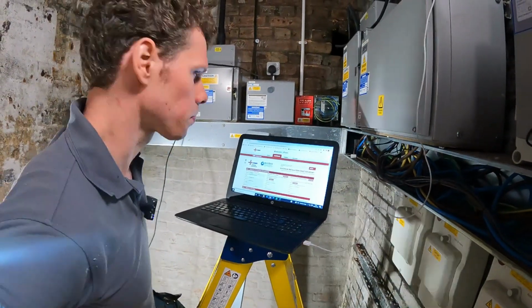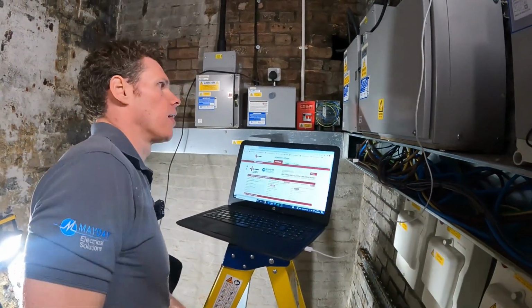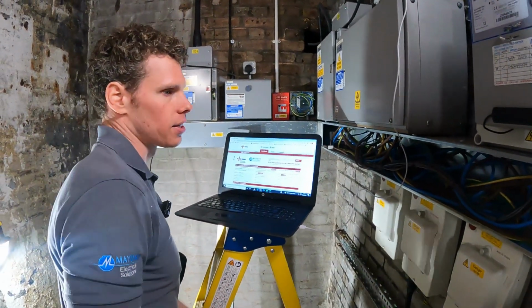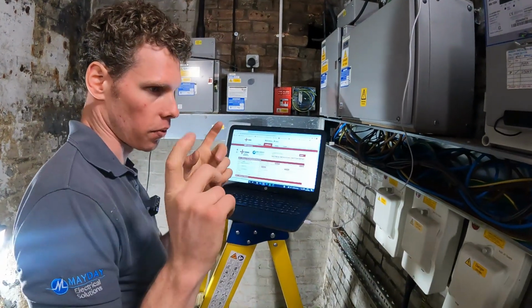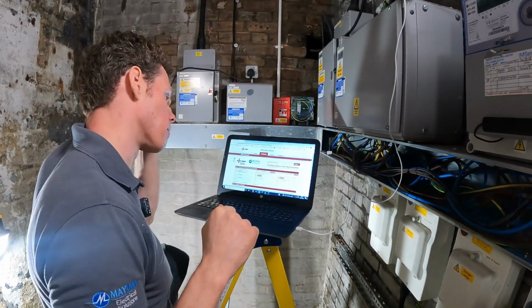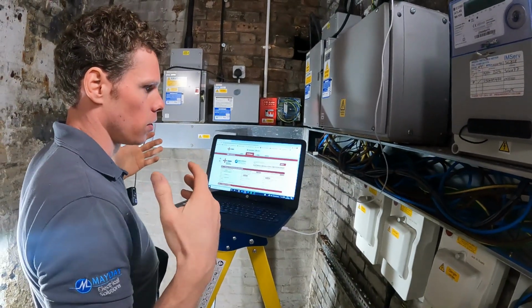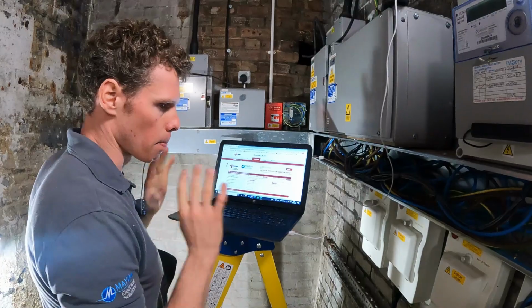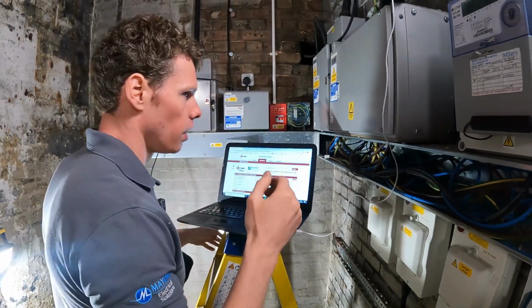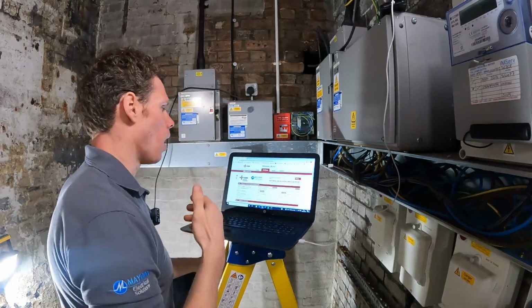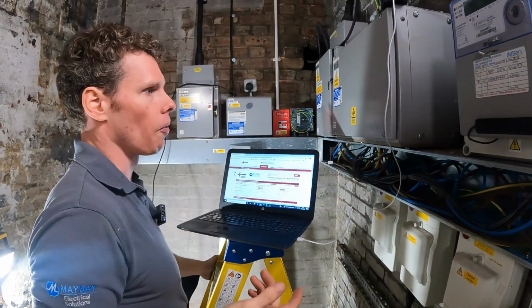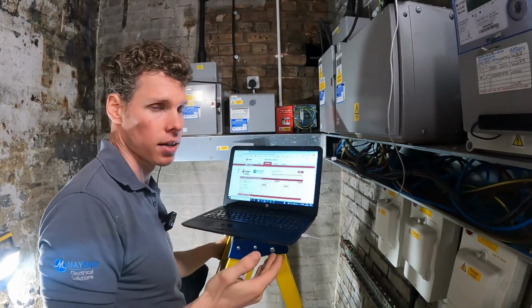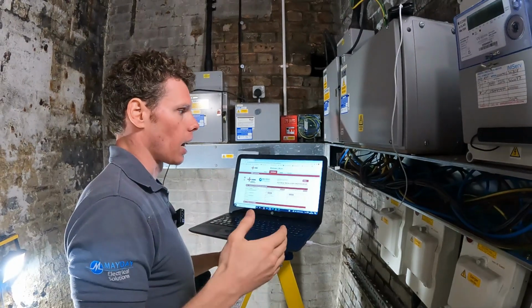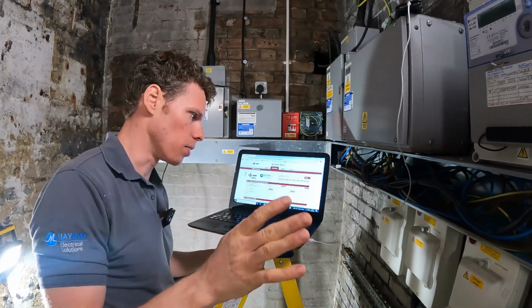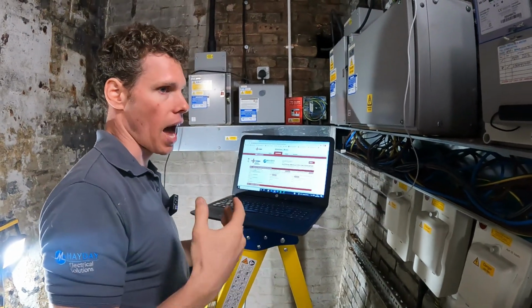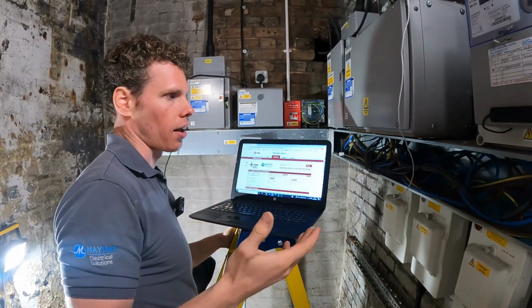When it comes to doing EICRs, commercially or domestically, you might get away with taking a photo of the fuse board and writing the test results down on your phone. But with larger installations that turns into a mess when it comes to doing the paperwork, so you're always better off doing it while on site. I tend to use the NIC online system - it used to be quite bad, but it's now pretty good. I used to use Amtech for a lot of my stuff, but I've stopped using it now because the NIC software is free and it's nearly as good as Amtech.